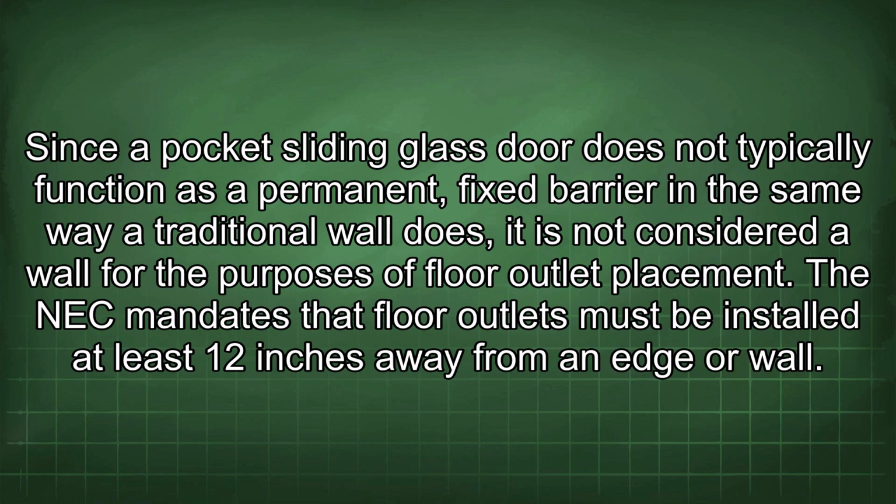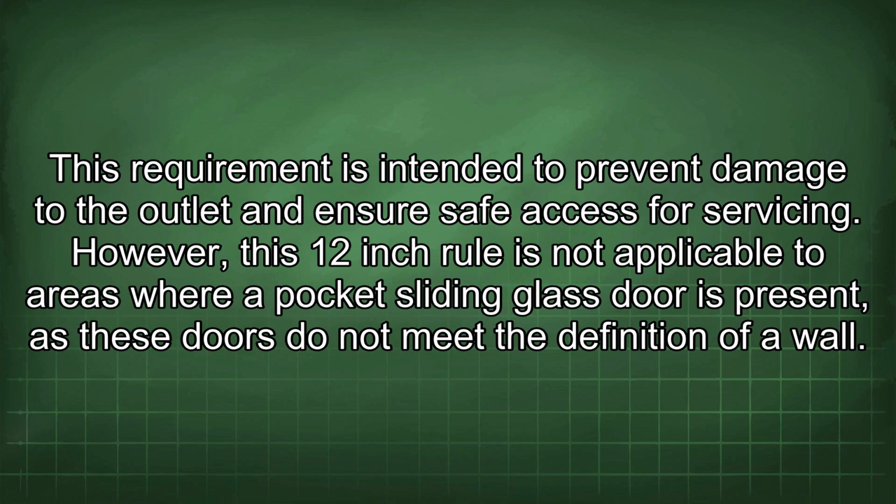The NEC mandates that floor outlets must be installed at least 12 inches away from an edge or wall. This requirement is intended to prevent damage to the outlet and ensure safe access for servicing. However, this 12-inch rule is not applicable to areas where a pocket sliding glass door is present, as these doors do not meet the definition of a wall.